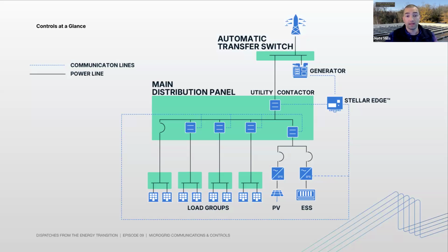When the battery recognizes that the utility contactor has successfully opened, it will switch from following the signals from the grid to forming its own grid by controlling voltage and frequency. That transition time, depending on the OEM of the battery, can take milliseconds, or it could take 10 to 15 seconds, depending on the size range and manufacturer. That transition from grid following to grid forming is also not necessarily controlled by the Stellar Edge.